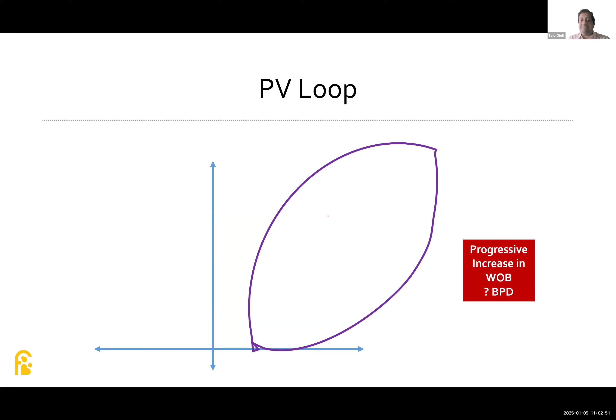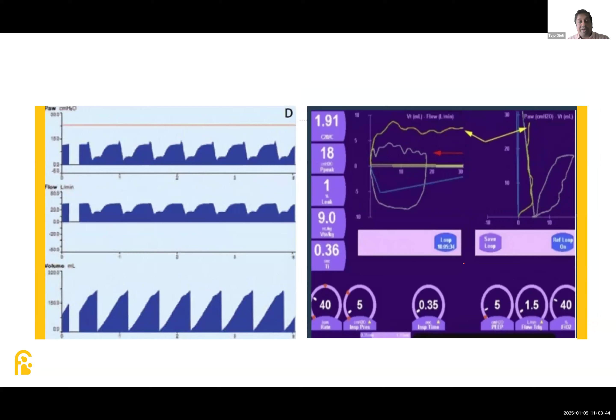Look at this case scenario. What happened here? Very chaotic. If you look at the scalar graphics and then compare it with the loop graphics, what is happening? This is the pressure, this is the flow, and this is the volume. Starting, but it is not sustained. Here also, flow is getting started, but it is not sustained. Pressure is getting started, it is not sustained. In the flow versus volume loop, you can see flow has started, but it has not touched anything. So here also, pressure has started to increase, but nothing is getting generated in terms of volume, or it is not coming back. We do not want these misadventures to happen in your unit, but graphics do help you.